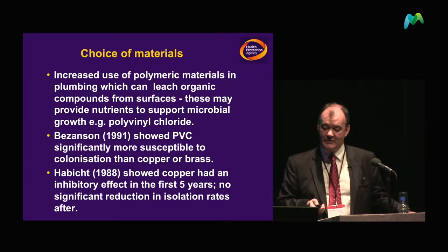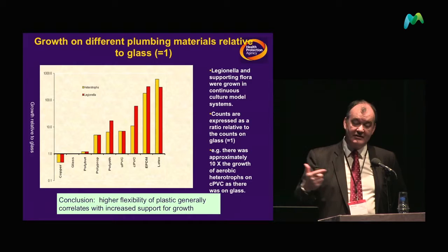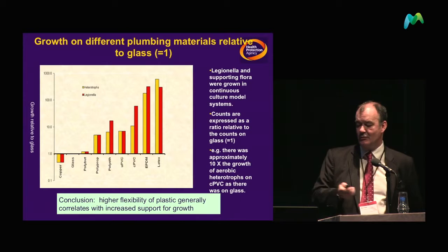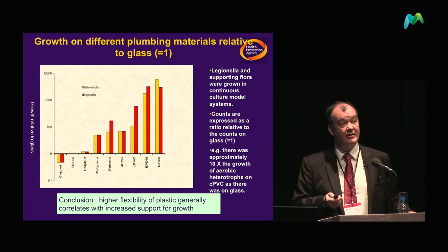The choice of materials is also important. This study looked at Legionella growth using different materials — latex is very good for growing Legionella, while copper will have a negative effect. The material you use in your water system could actually be fundamental in trying to control Legionella within a hospital or other environment.